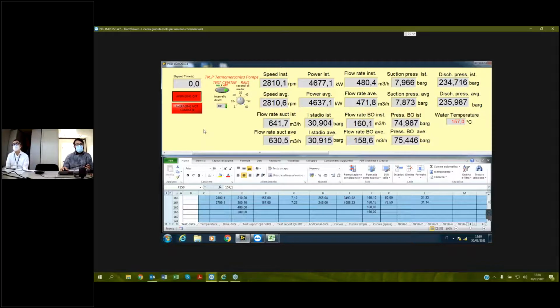The worksheet is used to recalculate all the other quantities that are necessary for the performance test, and these are very important quantities. For example, we have the hydraulic power for the machine and the hydraulic power for the bleed off. The sum of those is the hydraulic power of the machine. If we make the ratio between the hydraulic power and the overall power read by the instrument, this ratio is the efficiency of the machine itself. So this is a very important measurement.